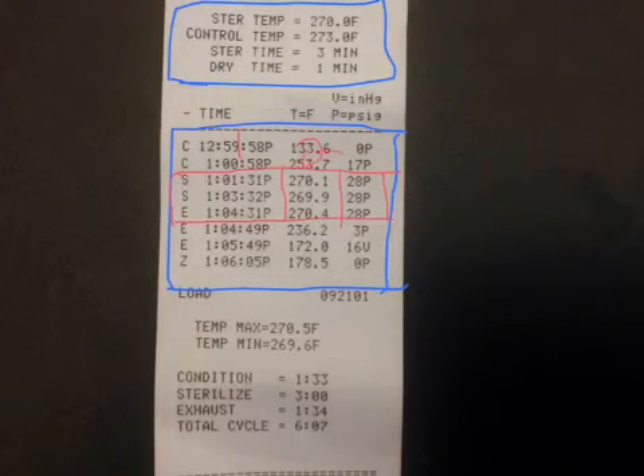So that information is in that first column. And column two is our temperature. Notice that it does not reach above 270 degrees until it starts the sterilization. Now there is one temperature here that's 269.9 that still would be considered the 270 degree mark, and that it stayed in column 3 above at least 27 psi. And so in this area you're going to see 27 to 30 psi is typically necessary to maintain the autoclave above 270 degrees. So when we're looking at this readout, we want to look at all three of these columns.